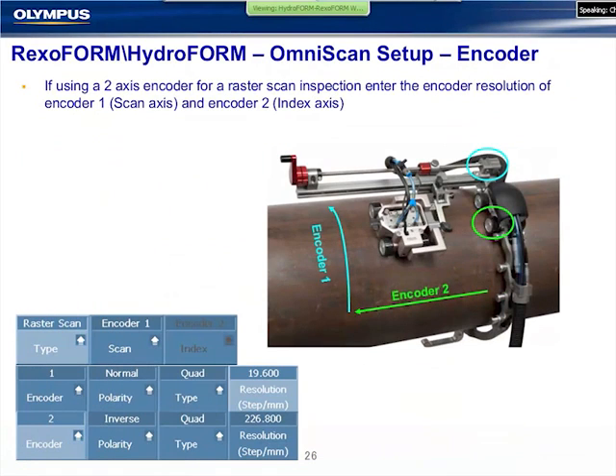And when we're configuring this in a two-axis scanner, we will select the raster scan and program encoder 1 and encoder 2. We will tell the software which encoder we want to assign to the scan axis, which is typically encoder 1. So this is the mechanical axis, and this is the electrical axis where we will step the buggy over 60 millimeters at a time.